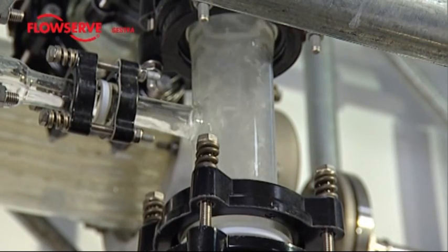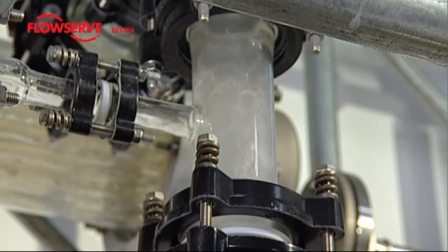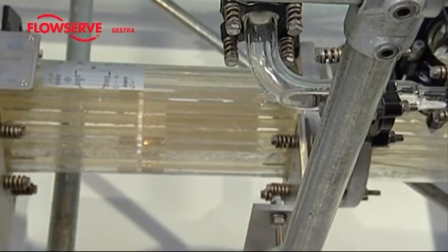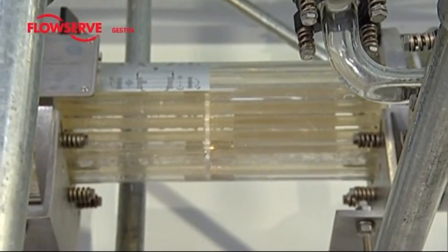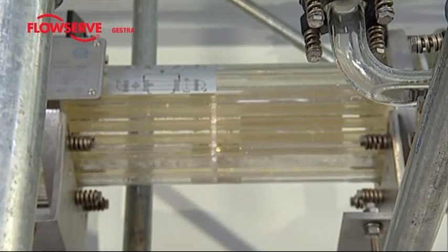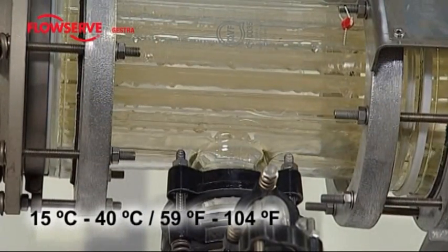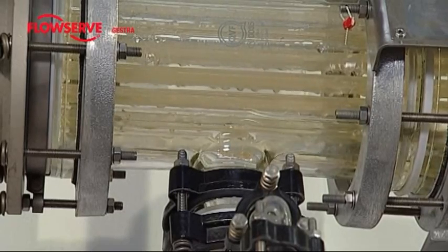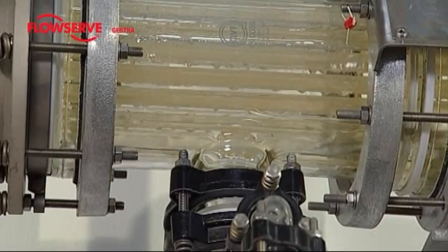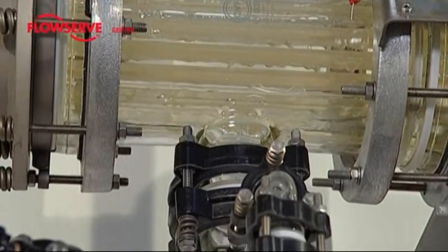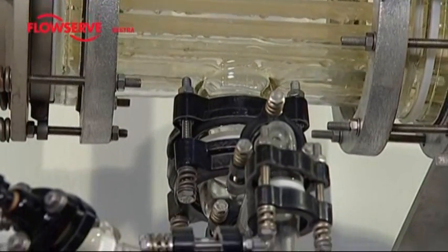Condensate drops can be seen. These are either entrained, in suspension, or flowing back into the steam generator. The saturated steam flows into the heat exchanger. In the heat exchanger, the tubes are charged with a cold medium, water in our model heat exchanger, which is then warmed up from about 15 to 40 degrees centigrade. The steam flows around the inner glass tubes, releasing its heat of condensation and forming condensate, which then falls down off the glass tubes. The condensate collects at the bottom and is discharged through the outlet.